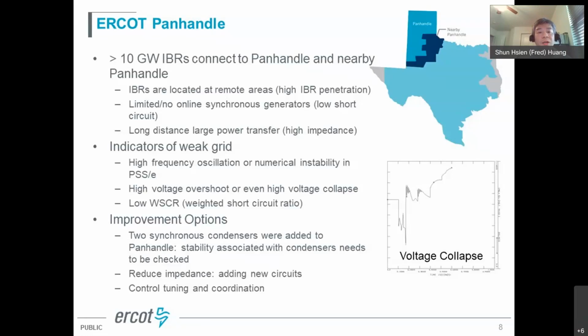So our practice right now is in Panhandle, when we identify it's weak, we put the condensers in. We did add two synchronous condensers in Panhandle to provide system strength and dynamic reactive support. And to echo what Nick mentioned in the beginning, the stability related to the synchronous condenser needs to be checked before you implement the condensers in the system.